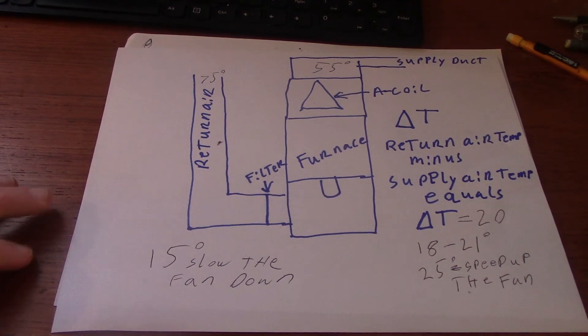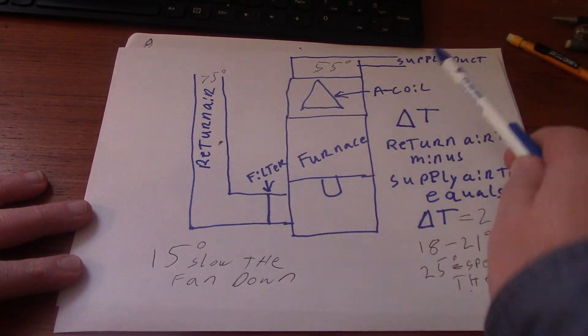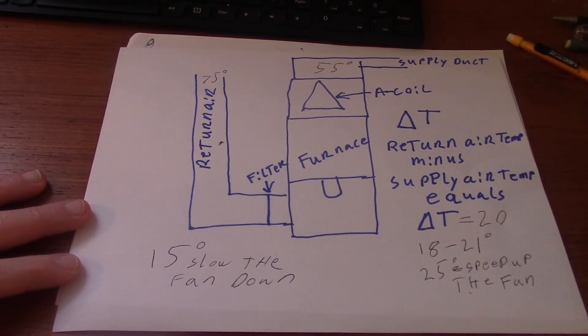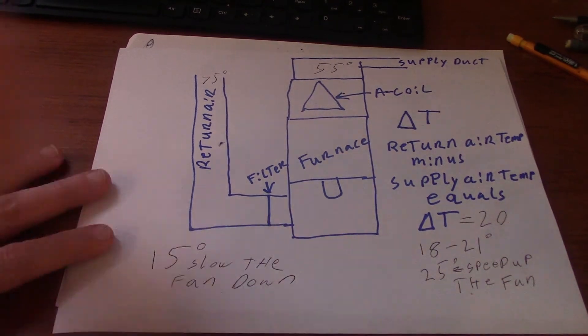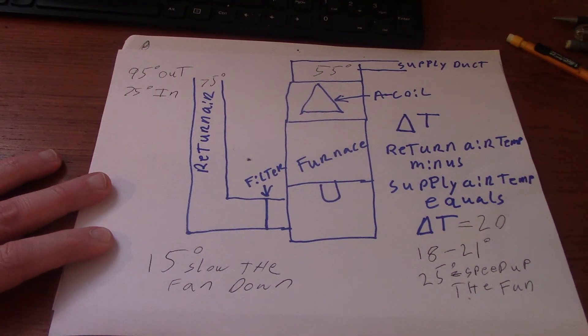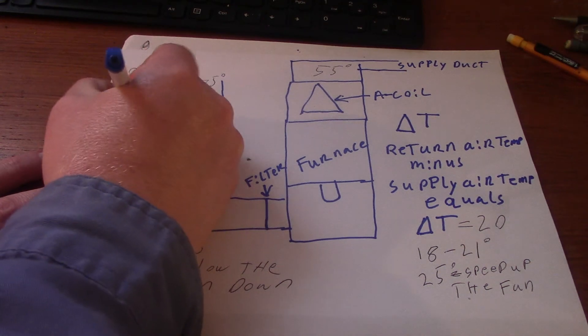And that's all it is. Return air minus supply air. These are generic parameters of 75 and 55. Remember your design conditions for an air conditioner: 95 degrees outside, 75 degrees inside, and around 55% relative humidity. So that's your design parameters and a little bit of info on the Delta T.